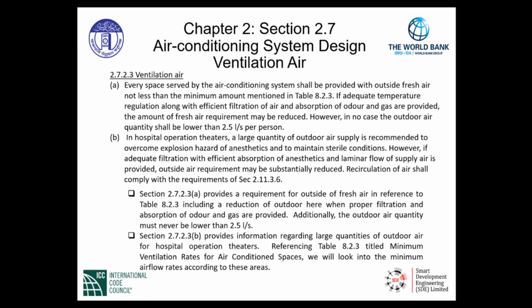Table 8.2.3 is referenced. We will take a look at Table 8.2.3 and work through a calculated example for ventilation, mechanical ventilation. As seen here, the minimum airflow quantity cannot be lower than 2.5 liters per second per person. We will find that there are a series of calculations that have to be made to determine how much outside air needs to be provided in a mechanical ventilation system. So we need this initial requirement as a basis for our design, installation, and final balancing of the system for verification.